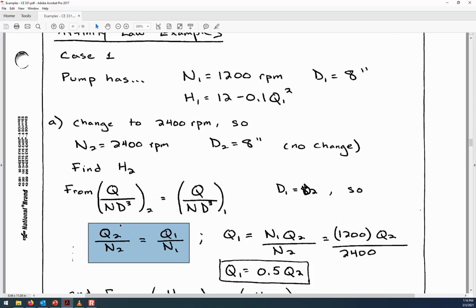So what's left is that the ratio of the flow rate of pump 2 to the rotational rate of pump 2 equals the flow rate of pump 1 to the rotational rate of pump 1. Solving for Q1 in terms of Q2, we get Q1 equals 0.5 Q2.